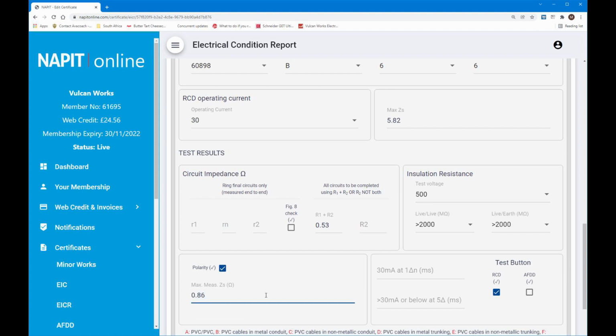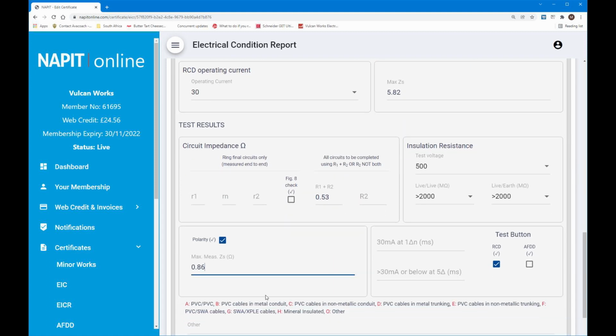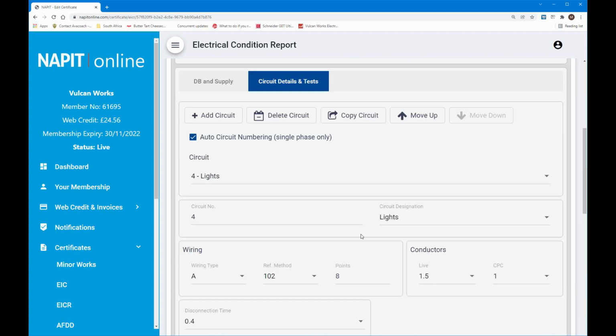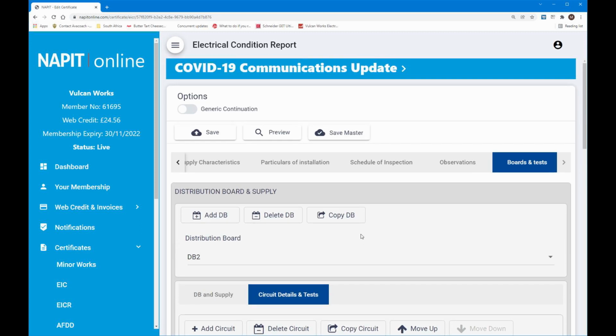Can I just add that the reading from the other consumer board gave me the same ZE reading as the main board, and that's only because the board for the conservatory is literally the other side of the wall. The distance was negligible, so I would have been shocked if the ZE reading was any different. So it isn't, it was 0.33, so just in case anyone wonders about that, no, the reading was the same. So anyway, sorry, I digress. So 0.86, well within the ZS for this. So that completes the test sheets for both of those boards.